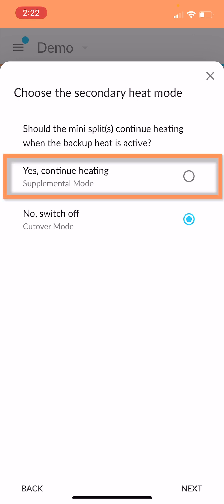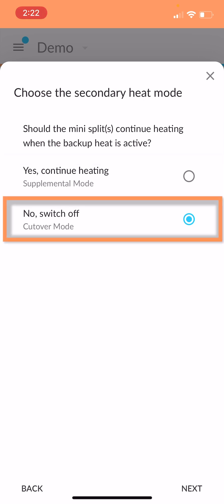You can set up the system so that the mini splits or the ductless heat pumps are supplemented by the second stage of that boiler. Or you could lock out the first stage so that when the boiler kicks on, the ductless units are turned off. I'd say this what we call the cutover mode, where you're locking out the ductless. That's the most common.